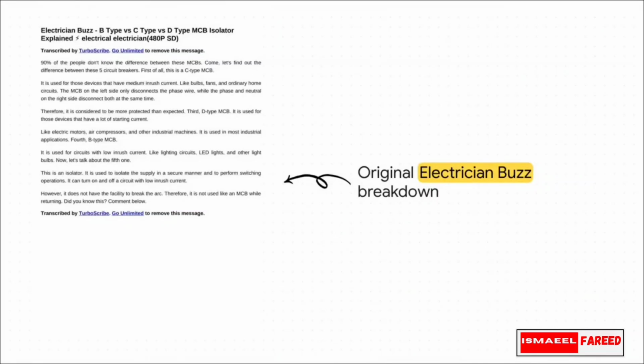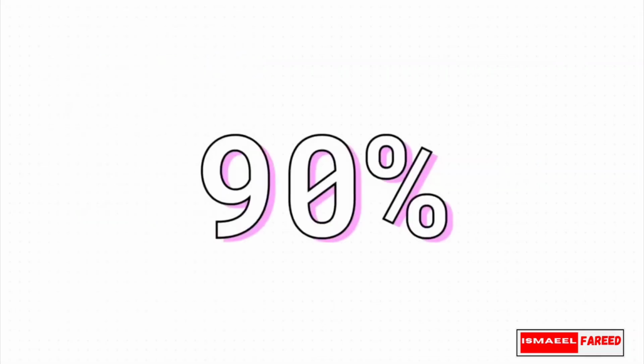They lay out the crucial operating differences between key circuit breakers and isolators. And what I really love is how they completely strip away the heavy jargon. It's all about what these devices actually do when the power starts flowing. Okay, let's dive into this, because right off the bat, there's a staggering statistic. According to our source, 90% of people have absolutely no idea what the difference is between these breakers. Most folks just see a switch and figure, hey, they all do the exact same thing. But using the wrong breaker for the wrong device, it's not just inefficient, it totally defeats the entire purpose of having a safety system in the first place.